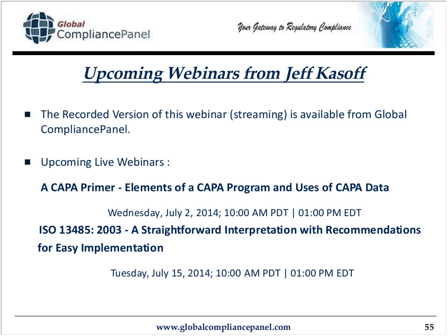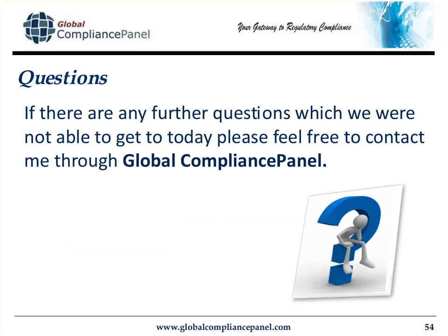The question reads, when is clinical data required? Interesting question. Clinical data is only required when you feel that you're unable to, by bench testing, provide data of safety and efficacy. So with regard to safety, you can perform biocompatibility testing in most cases on your device. And when it comes to efficacy, if your bench testing, if your in vitro testing, if you will, is insufficient, you will need to perform clinical testing. So I hope that clears that up.